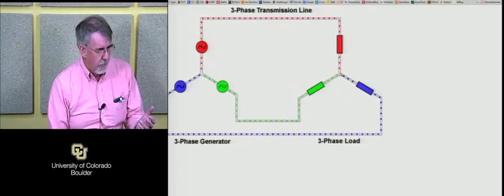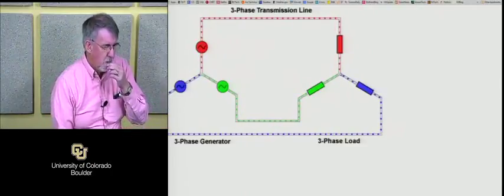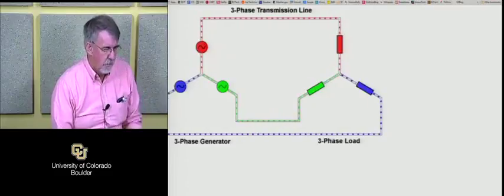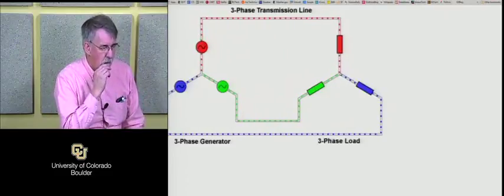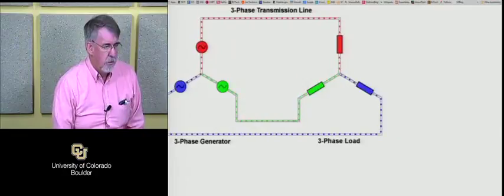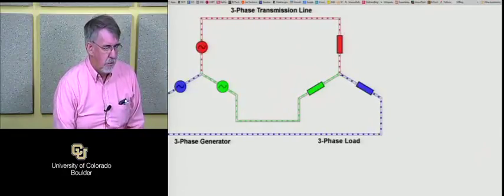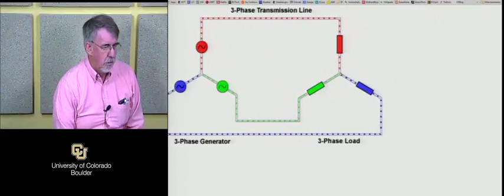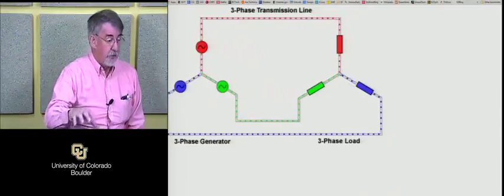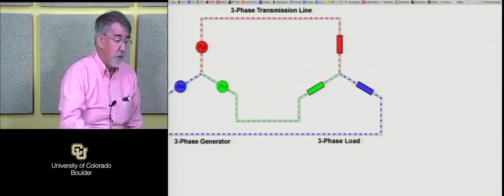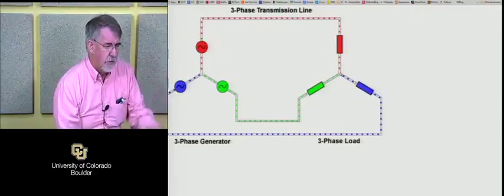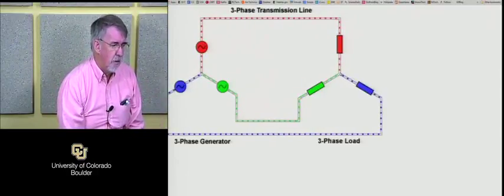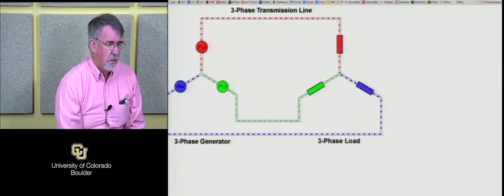So like a 120/208 system is three 120 legs, all 120 line to ground, and 208 line to line. A 120/240 three-phase system is two 120 lines with, I think, a 208 line to ground. We'll talk about those in a minute. I think that's what she means by the wild leg, the high leg.